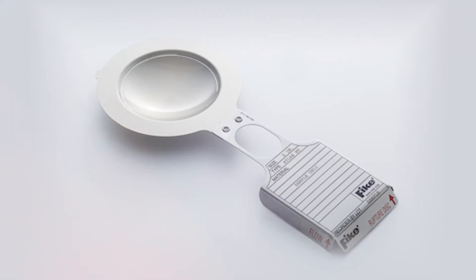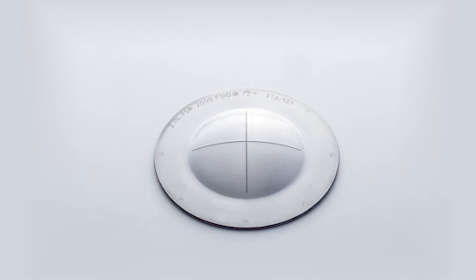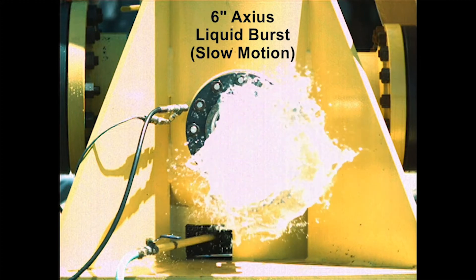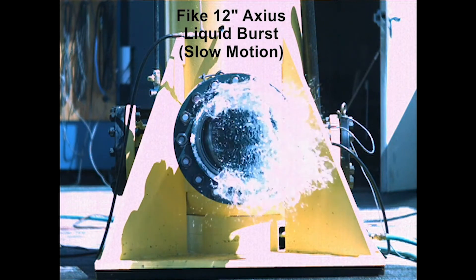A rupture disc is a specific kind of non-reclosing pressure relief device. The neat thing about rupture discs is that they react to the overpressure situation in a matter of one or two milliseconds, so they open up instantaneously when called upon.